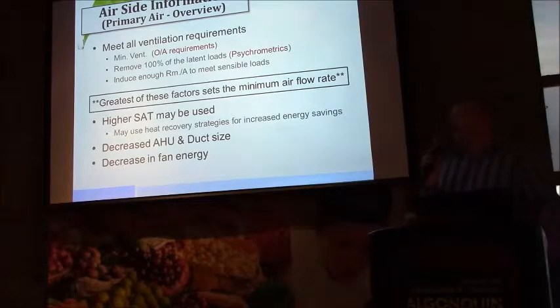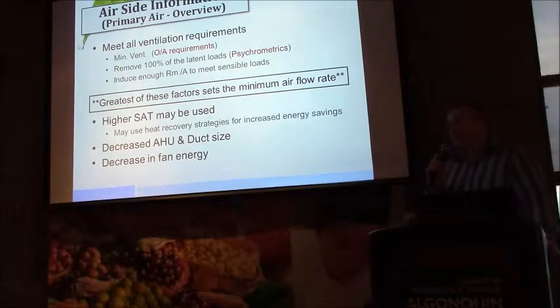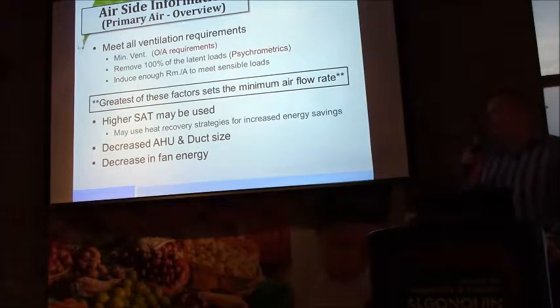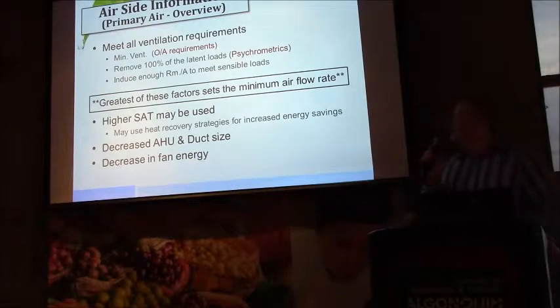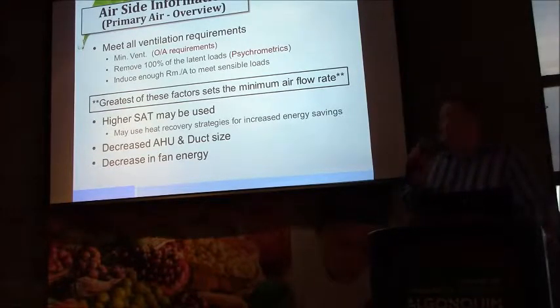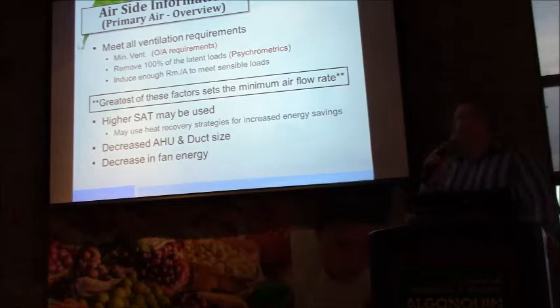But the minimum primary air that we need to supply to the active beams is governed by the greatest of the following three elements. The minimum ventilation that's required by code, in terms of ASHRAE Standard 62. The air that we need to offset the latent loads in the space is the second element. And that's really governed by the design decisions of the design consultant relative to how dry or dehumidified the primary air can be. How dry we can make the primary air relative to the evaporator coil. And there are energy consequences, obviously, and capital costs to make that primary air drier.